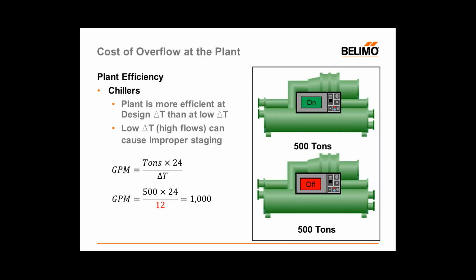What happens, though, if I have a low delta T? Let's say I go to 8 degrees of delta T. What does my flow look like? Well, because flow and delta T are inversely proportional when my load is fixed, this big of a reduction in delta T causes a huge increase in GPM, and in this case, I now require 1,500 gallons a minute. And likely what has happened is that I have staged a second chiller because I need additional pumping capacity to get to 1,500 gallons a minute, even though I didn't need my second chiller to increase the load capacity of my plant. And so this is what we talk about when we say improper staging.